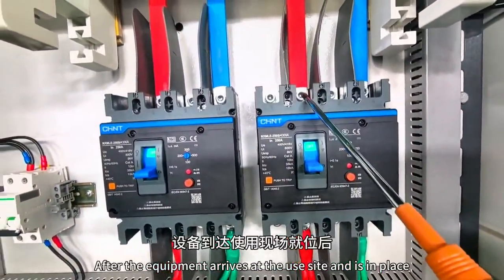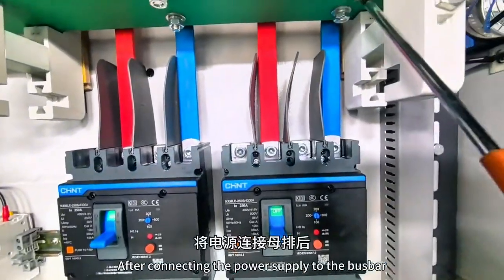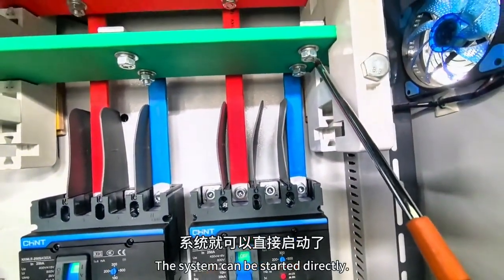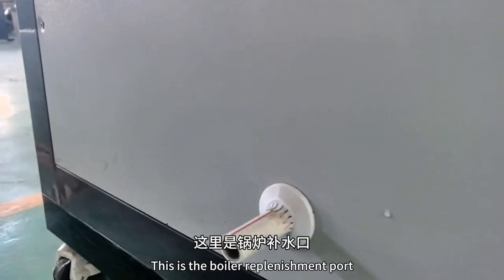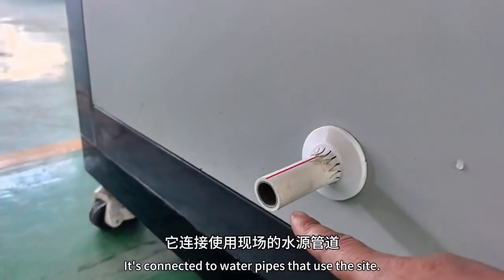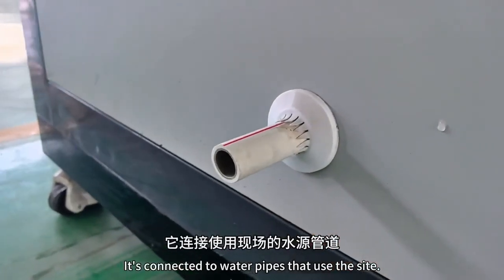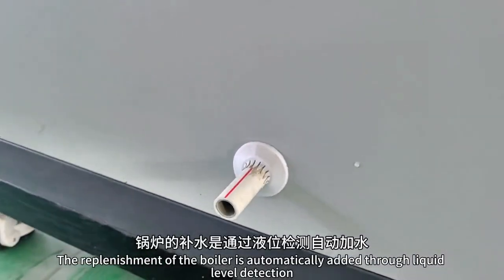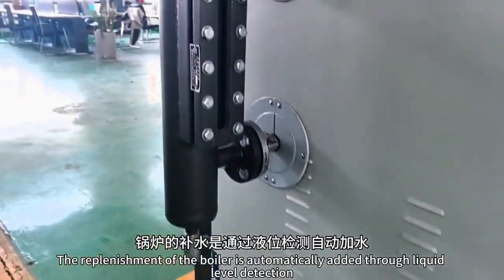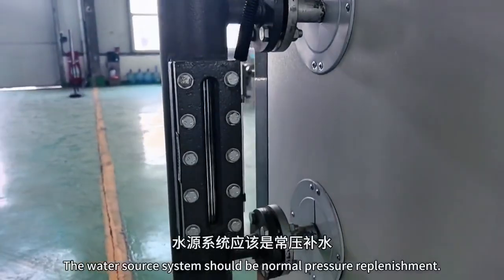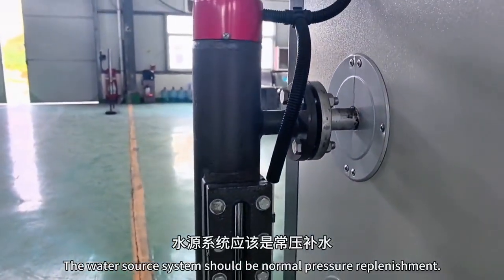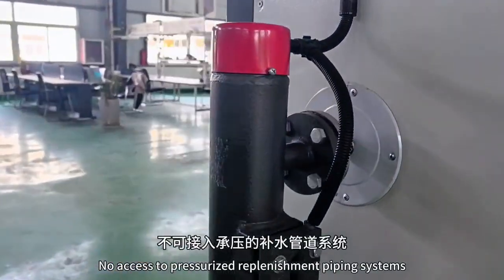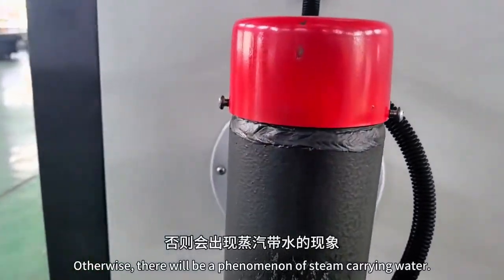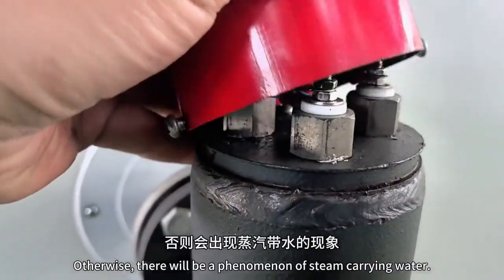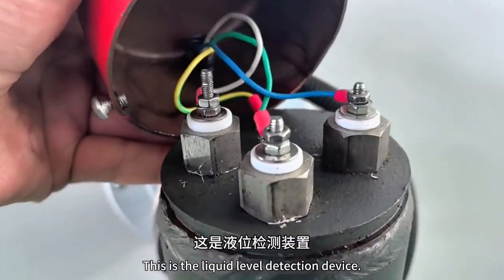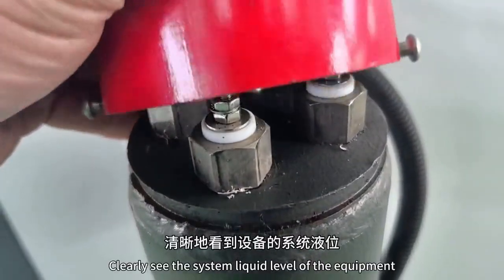After the equipment arrives at the usage site and is in place, the system can be directly started by connecting the power supply to the busbar. This is the boiler water supply port, which is connected to the water source pipeline on site. The boiler water supply is automatically added through liquid level detection. Therefore, the boiler water supply system should be atmospheric pressure water supply and cannot be connected to a pressurized water supply pipeline system, otherwise steam carrying water may occur.